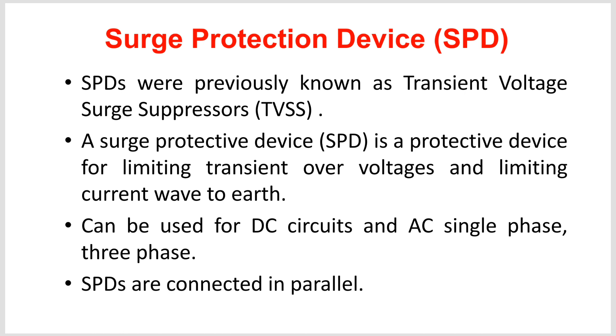Now there are different types of SPDs: Type 1 SPD, Type 2 SPD and Type 3 SPD. What is the difference between these types of SPDs? We'll see this here. Type 1 SPDs are designed for high risk zones and are characterized by 10 by 350 microsecond waveforms. Like if your industrial building is to be protected from direct lightning, then you will use Type 1 SPDs.